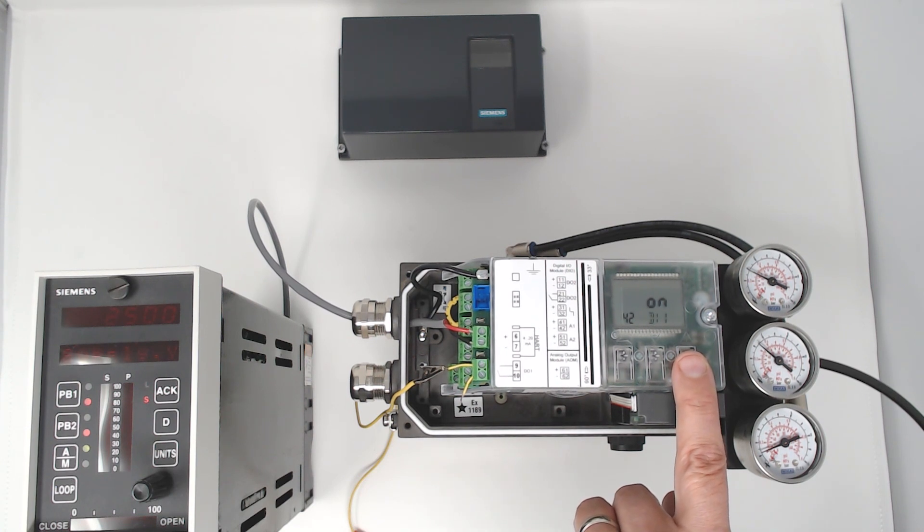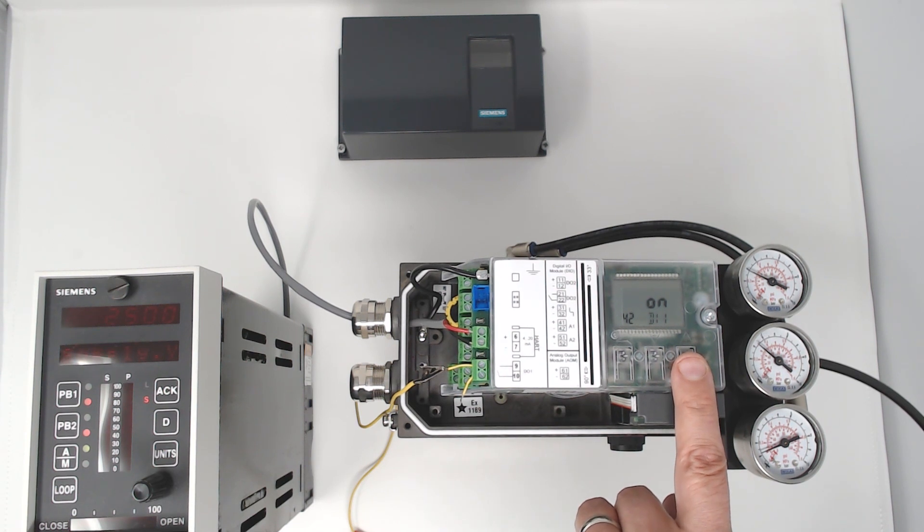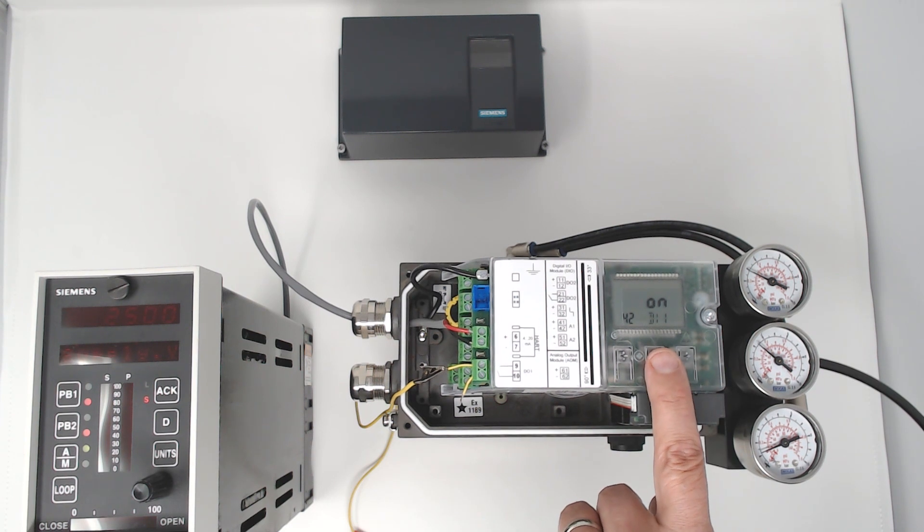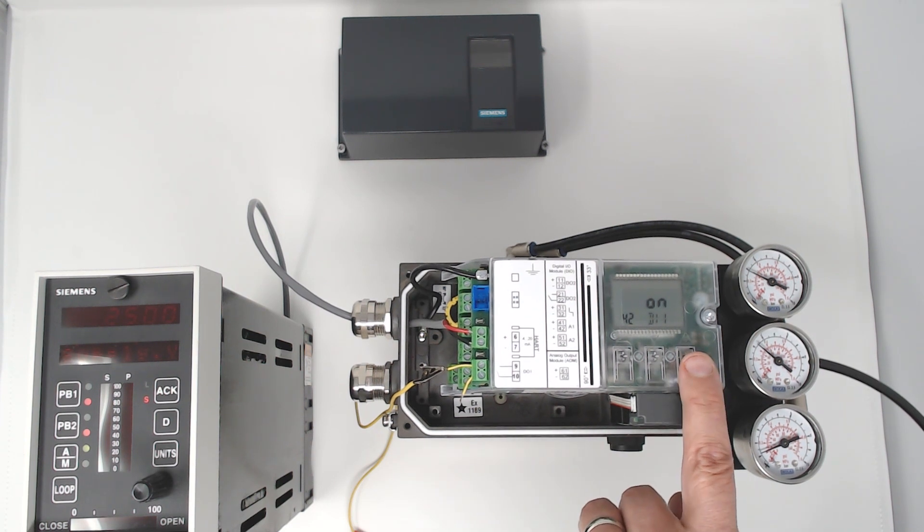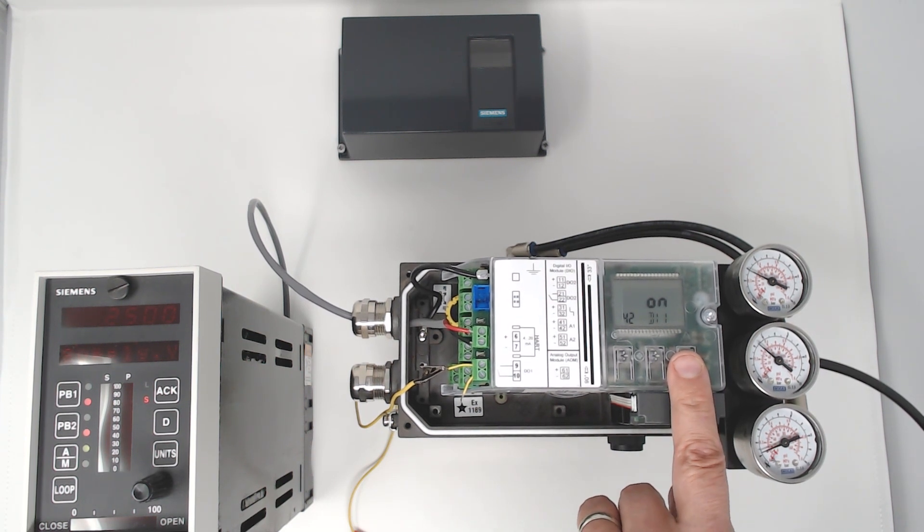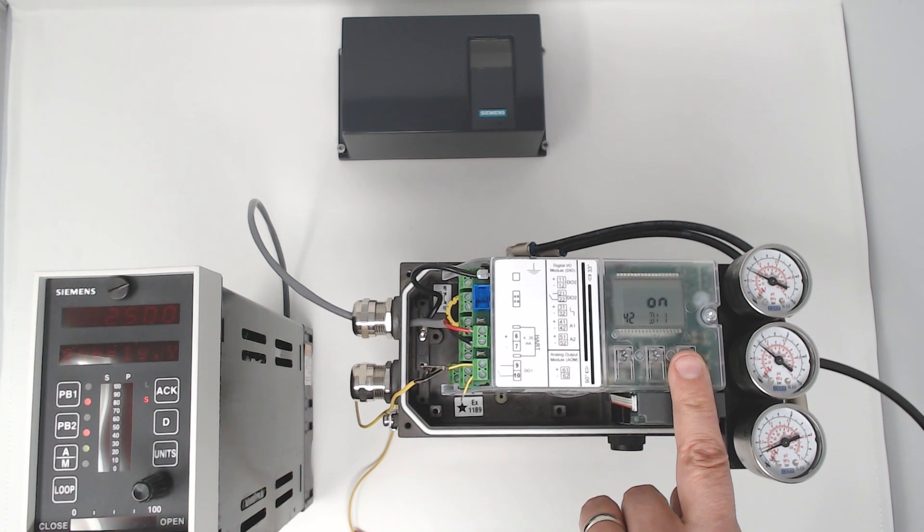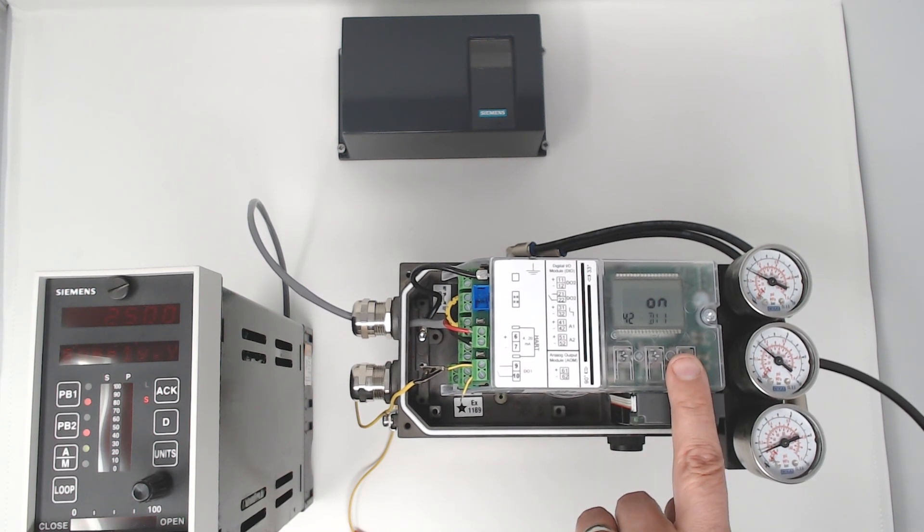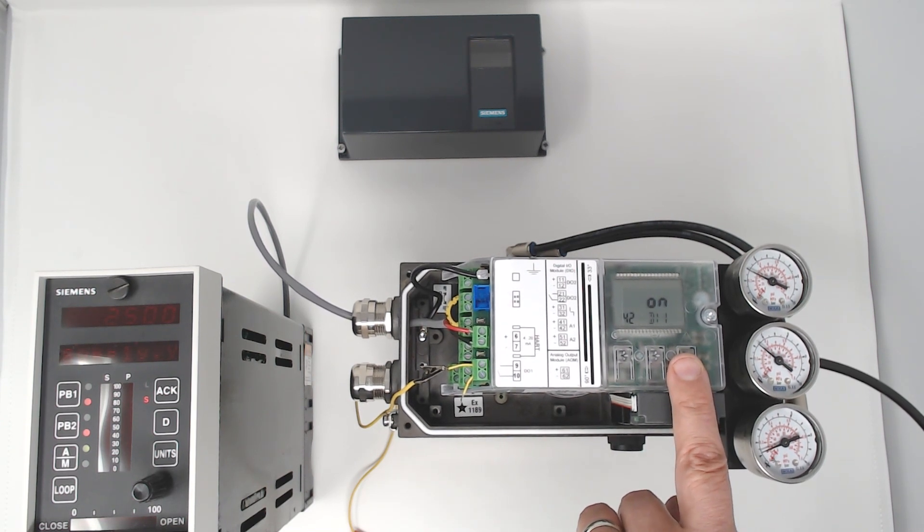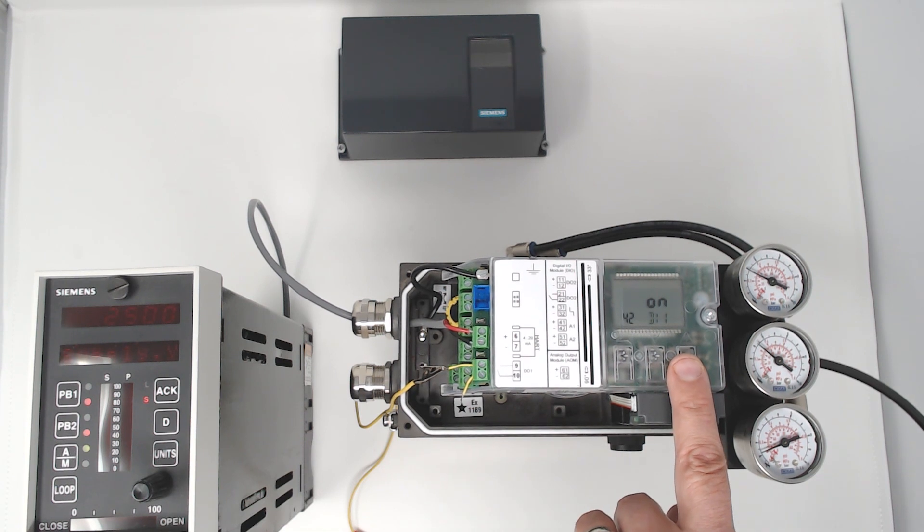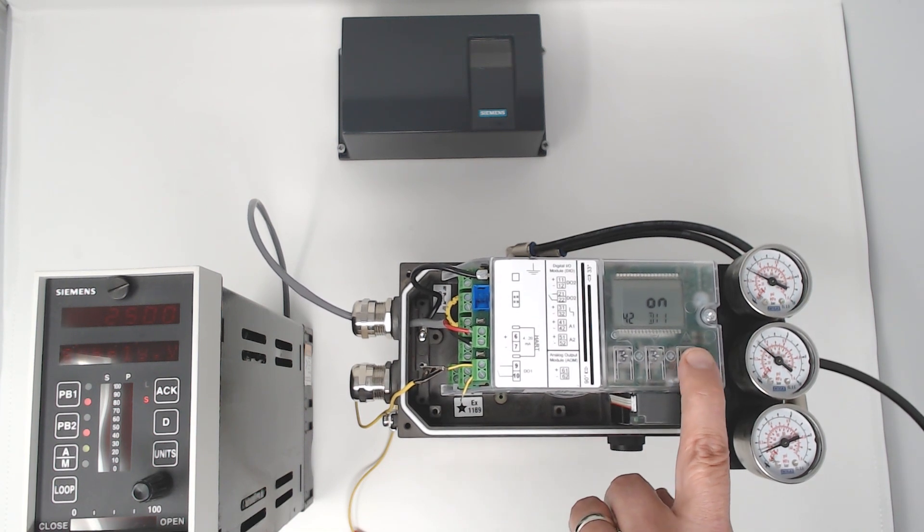That can be communicated through HART, Profibus, Foundation Fieldbus, or if you have the alarm card, can be communicated through the fault output. This is useful for if you have a local indicator or a local alarm on the process near this valve, that status of that alarm can be communicated back to your control room.